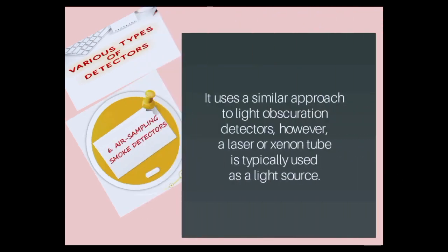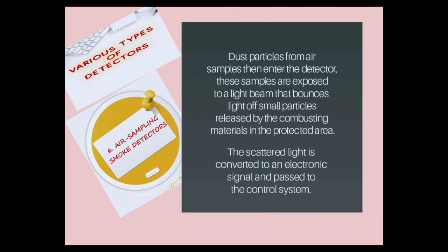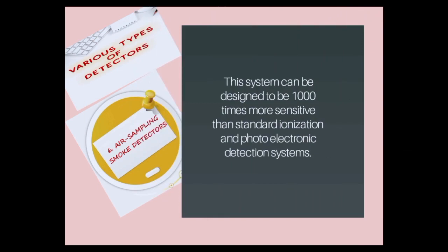The sixth type is the air sampling smoke detectors. It uses a similar approach to light obscuration detectors. However, a laser or xenon tube is typically used as a light source. In addition, dust particles from air samples enter the detector. These samples are exposed to a light beam that bounces light off small particles released by the combusting materials in the protected area. The scattered light is converted to an electronic signal and passed to the control system. This system can be designed to be 1,000 times more sensitive than standard ionization and photoelectric detection systems.